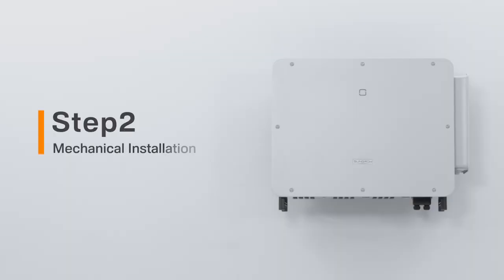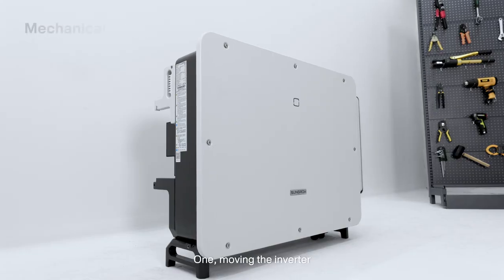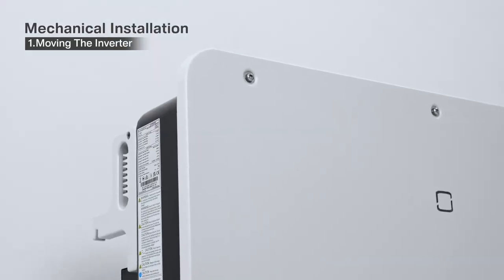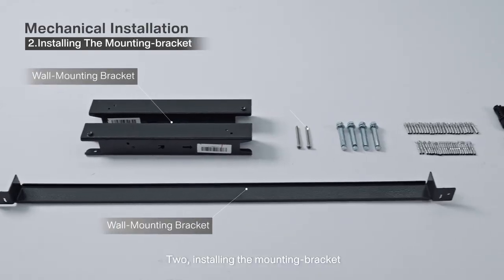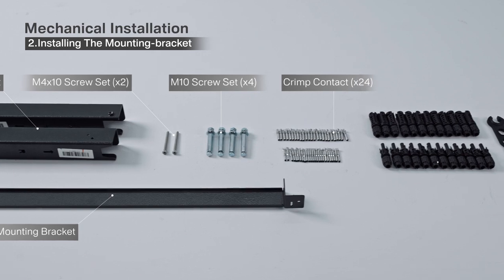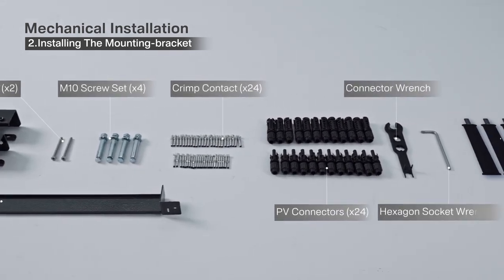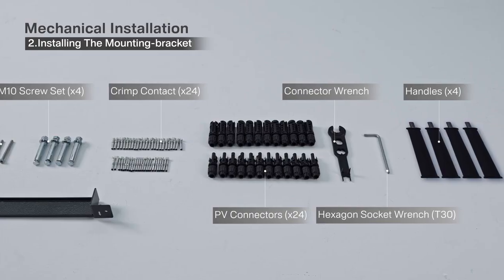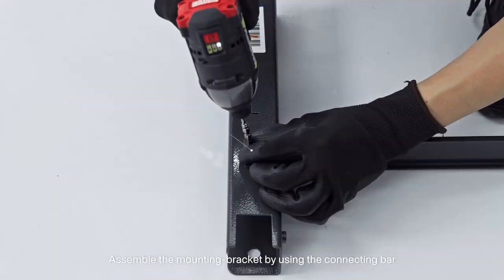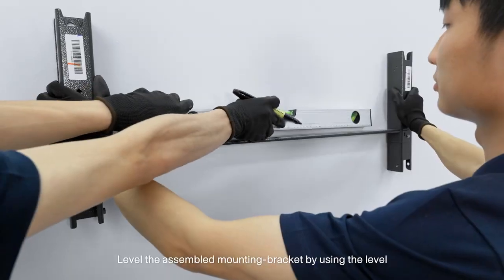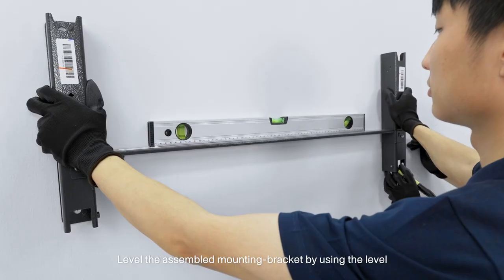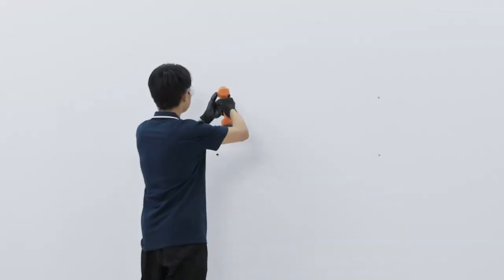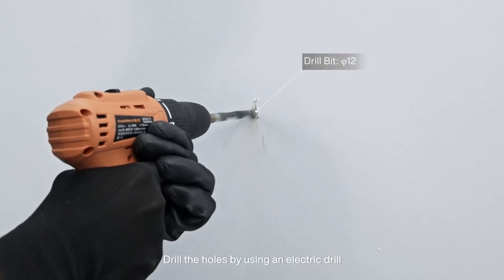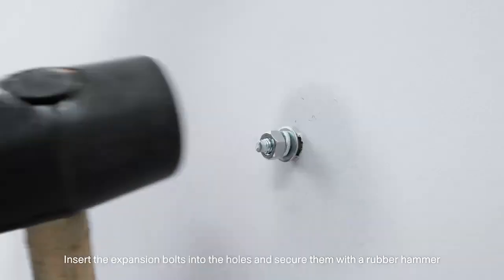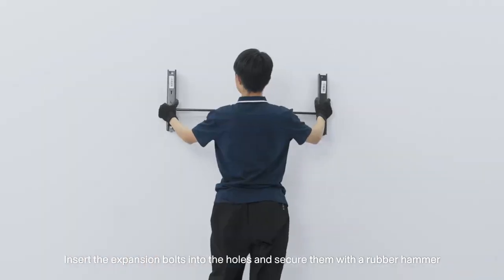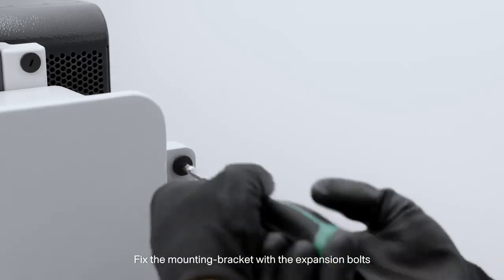Step 2. Mechanical installation. 1. Moving the inverter. 2. Installing the mounting bracket. Assemble the mounting bracket by using the connecting bar. Level the assembled mounting bracket by using the level and mark the positions for drilling holes. Drill the holes by using an electric drill. Insert the expansion bolts into the holes and secure them with a rubber hammer. Fix the mounting bracket with the expansion bolts.